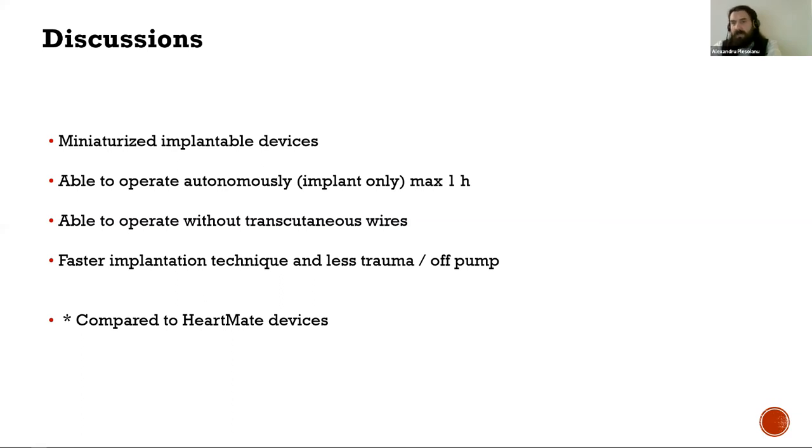Further investigation, anyway, must be performed to confirm the mathematical calculus of the pump by computed fluid dynamics and in vitro testing. Furthermore, the concerns regarding stabilization of the bearing system and the risk associated with transcutaneous energy transmission must be addressed.